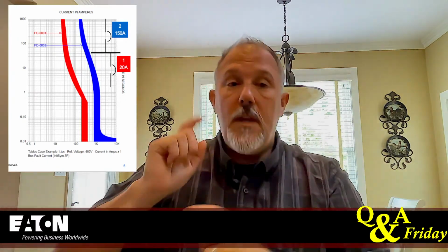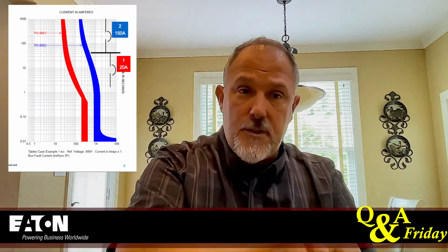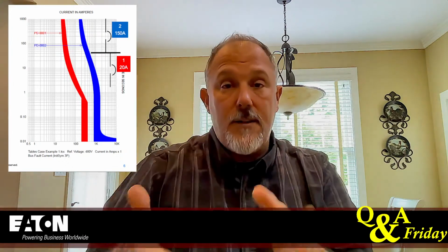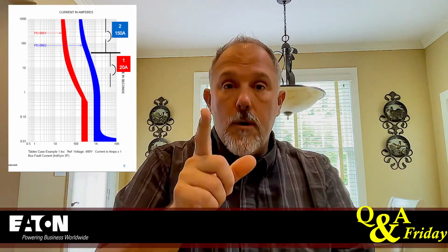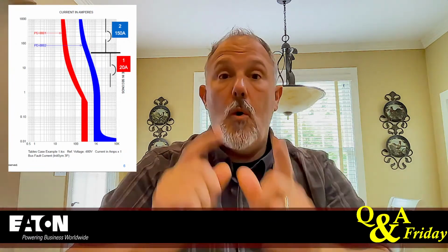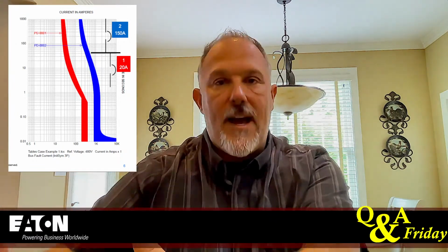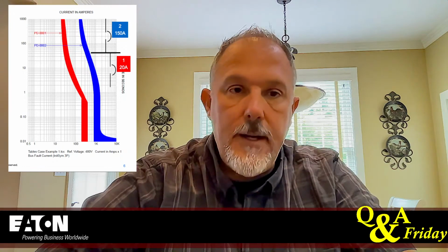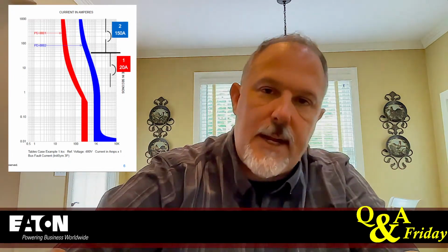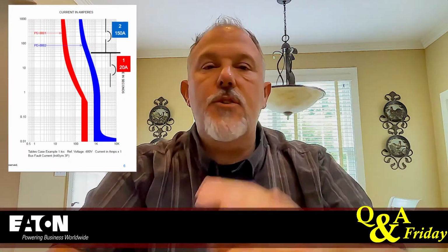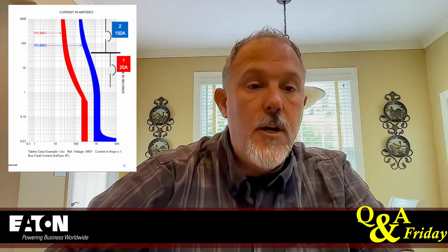So you've got 3 options. Increase the upstream overcurrent device, which adds complications, increases the conductor, possibly increases the upstream panel board. You might have to increase the downstream panel board. And it also increases fault current. Or you can put a 1-to-1 transformer to reduce the fault current, or you can make the downstream device go faster. And if it's a breaker solution, I don't know that there's any other breaker faster than that BAB20. But if you had, I don't know, an insulated case, you can try to put a molded case downstream, but then, in any case, you just want the downstream device to go faster. So those are your options to get this to selectively coordinate.